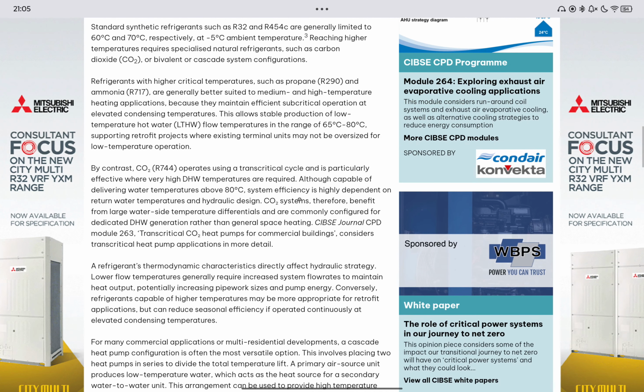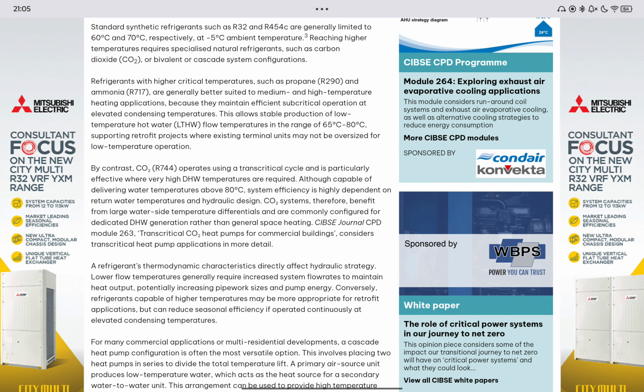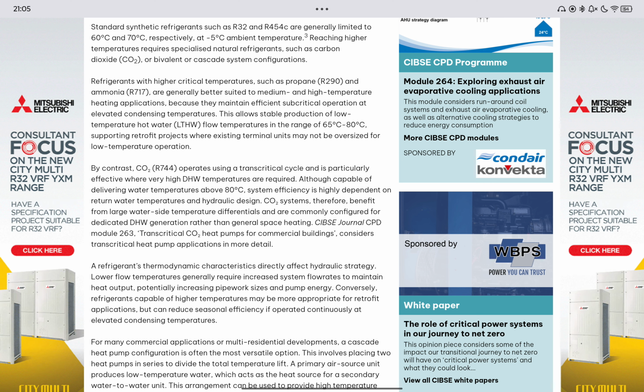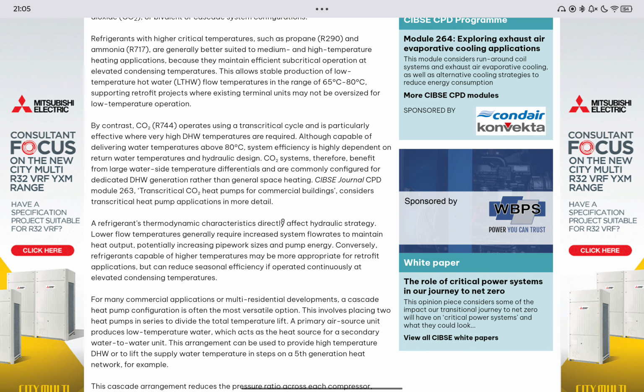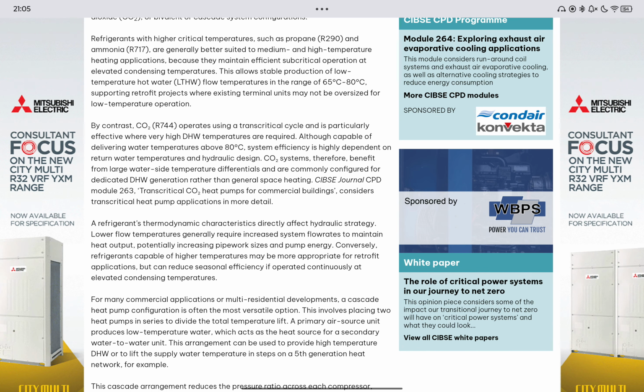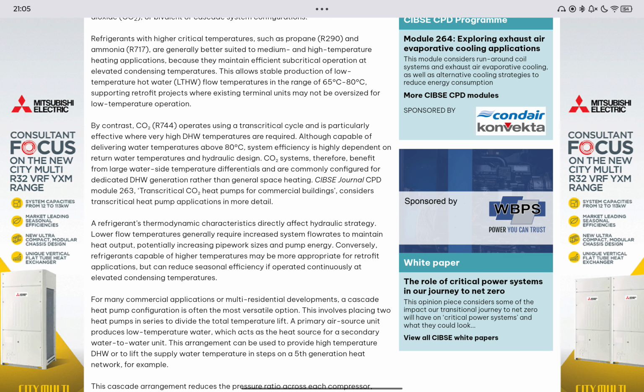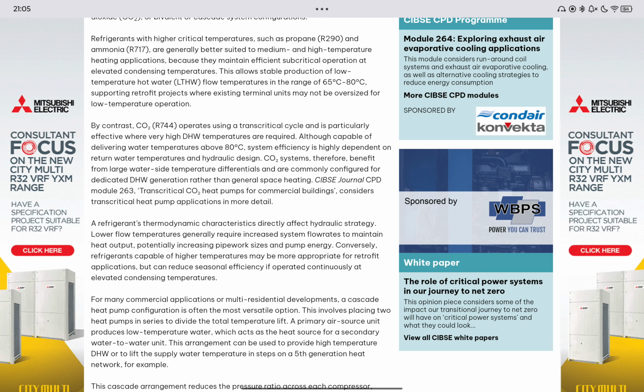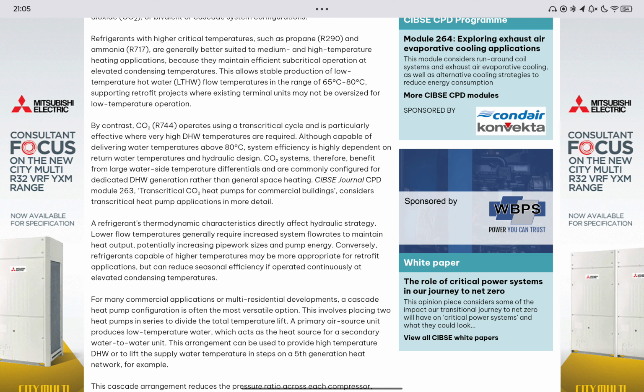In contrast, CO2, or R744, operates using a transcritical cycle and is particularly effective where very high DHW temperatures are required. Although capable of delivering water temperatures above 80 degrees C, system efficiency is highly dependent on return water temperatures and hydraulic design. CO2 systems therefore benefit from large waterside temperature differentials and are commonly configured for dedicated DHW generation rather than general space heating.